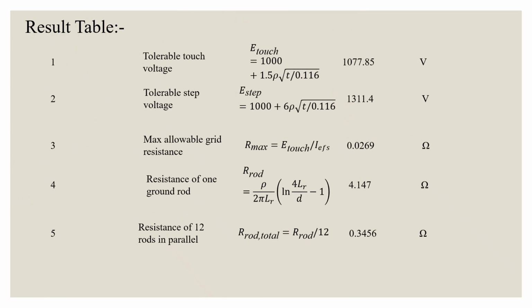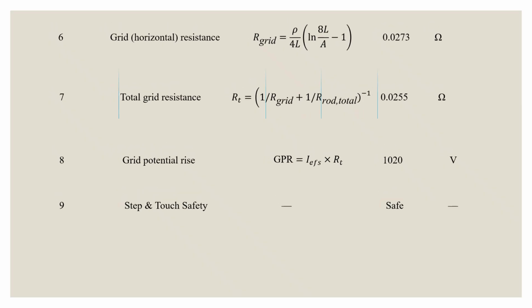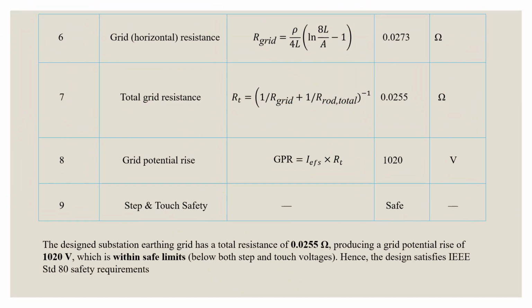Now, once we have calculated all the parameters and their values, let's make a result table. Here are all the values with their formulas and with their units. So the final result shows a grid resistance of 0.0255 ohm and a potential rise of about 1020 volts, which is below the permissible limits. Thus, the design is considered safe and compliant with the IEEE standards and requirements.